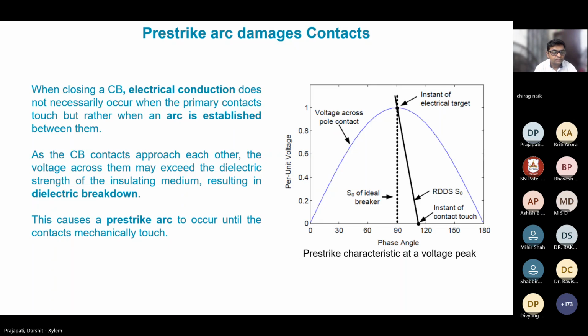So in essence, while shunt opening, capacitor closing, and other switching operations are necessary for system control, they introduce significant stresses on the breaker contacts. Understanding and mitigating this effect is critical for extending the contact life and ensuring reliable operation.